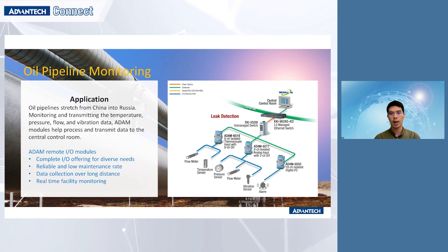However, ADAM remote I/O modules help process and transmit temperature, pressure, flow, and vibration data to the central control room miles away. For example, the ADAM 6018 is an excellent temperature data acquisition module with 8 thermocouple input channels.